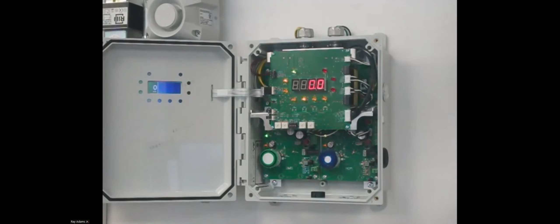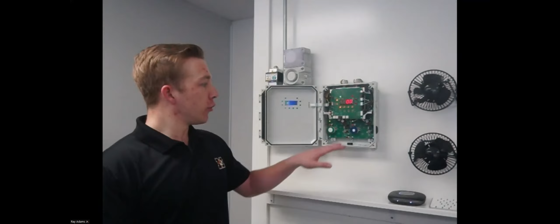With our standalone detector, probably 90% of the time when you're dealing with vehicle emissions, you're looking at a combination of CO and NO2 within a facility. So you'll have two sensors inside one housing, allowing you to monitor both gases without running wiring up to a second unit that may be up at the ceiling. Taking that further, not many manufacturers allow 4 sensors on one standalone. A few manufacturers let you have a third remote sensor, but in vehicle emissions you're dealing with CO and NO2, and that third sensor doesn't get you both gases.